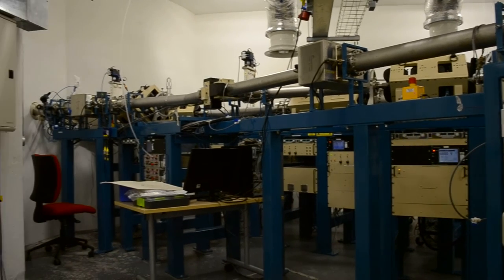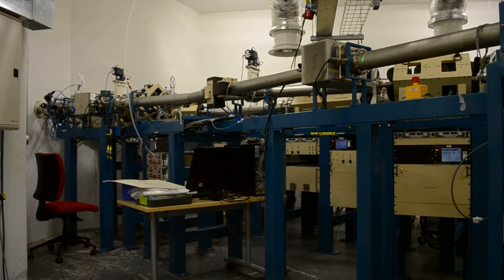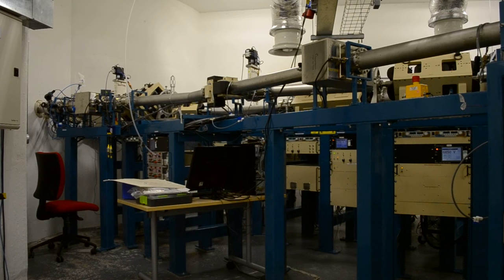These are the different beam lines. This one is the ion pump, meant to provide along the line the ultra-high vacuum of 10^-7 Torr.